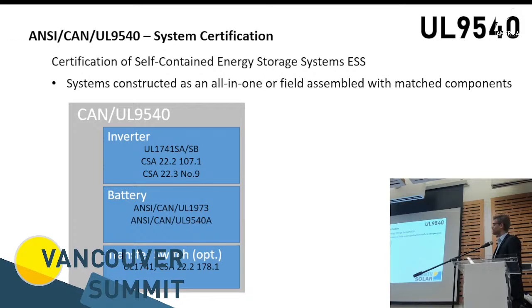The UL 9540, as I mentioned, is a system certification. So it's no longer just a certification of one component and then another component and then another component on their own. Like, for example, a solar system, you have the certification for the solar inverter. The solar panels have their own certification, and your racking system has a totally different certification for the grounding and whatnot. Now you bring that all together and form a system, and you have one certification that pretty much certifies the function between those components in that system.